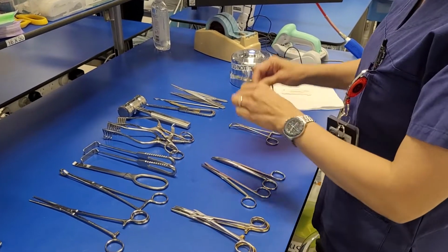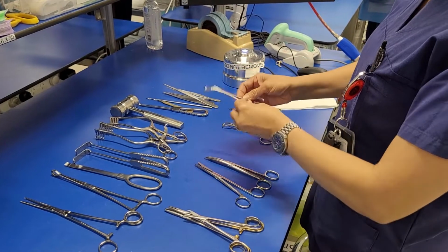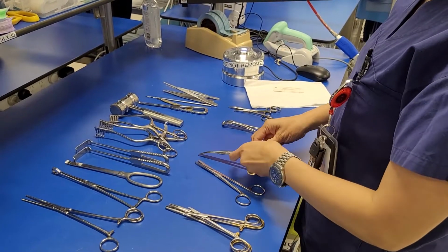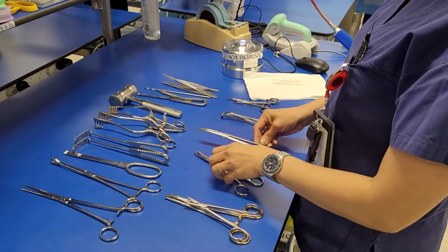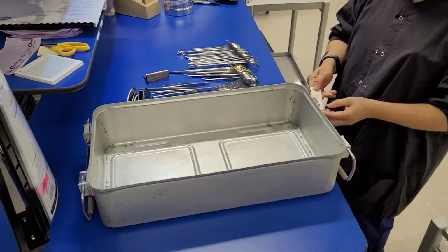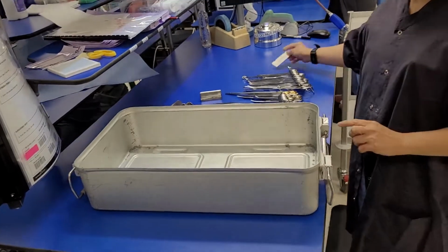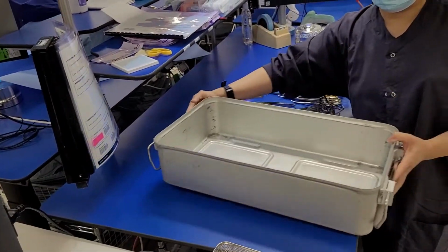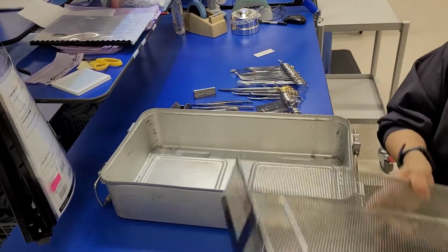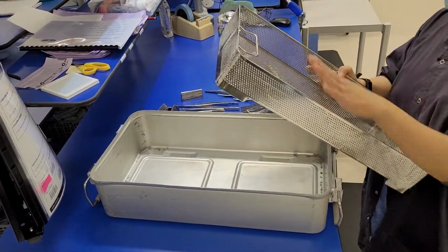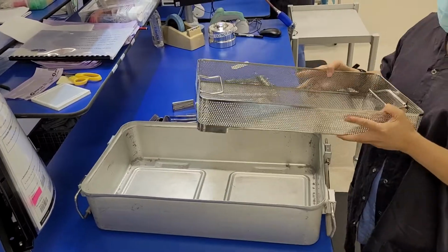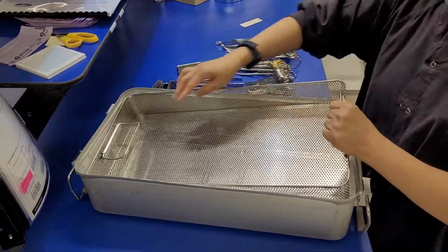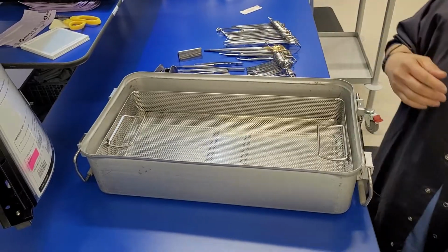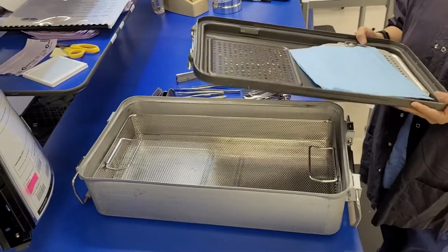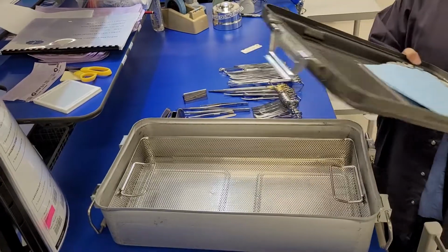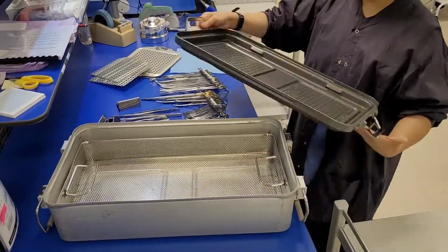RMDs that are inspected and packaged should be fit for purpose to meet all safety requirements to avoid cross-contamination of RMDs. Inspect the integrity of the rigid container. Verify the top surface and edges of the container and lid are free from dents and chips. Check the inner is not overloaded and that there is sufficient room between the basket and under the side of the lid. Follow the correct steps to install the filter and ensure that it is properly in place. Missing or wrong filters can lead to contamination of the contents, as can lids that don't fit properly.